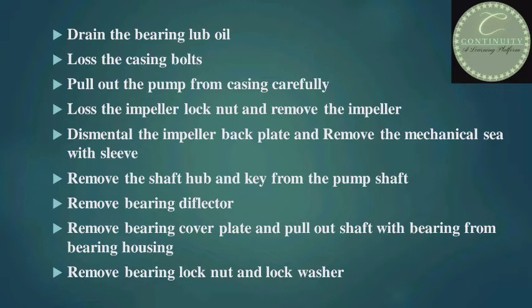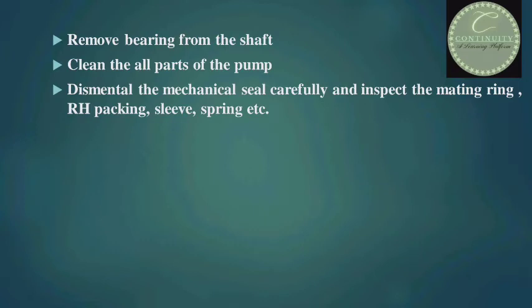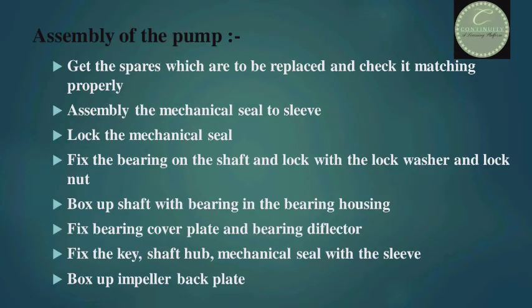Remove the bearing lock nut and lock washer and remove the bearing from the shaft. Clean all parts of the pump. Dismantle the mechanical seal carefully and inspect the mating ring, packing, sleeve, and spring. These are the complete steps of disassembly of the centrifugal pump.